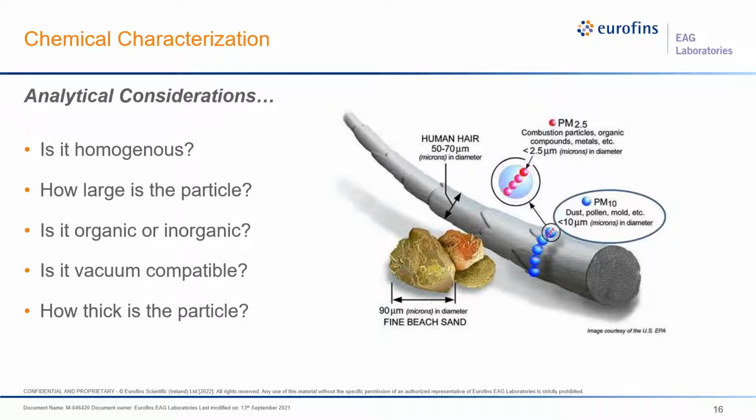Is the sample vacuum compatible? That's a very good question you want to consider first, because some techniques require a high vacuum chamber. You don't want to put in samples that are not compatible. It may have water or liquid trapped inside it, and it could explode in the instrument when it hits high vacuum. Not only do you lose your particle, you may very likely contaminate your instrument as well.